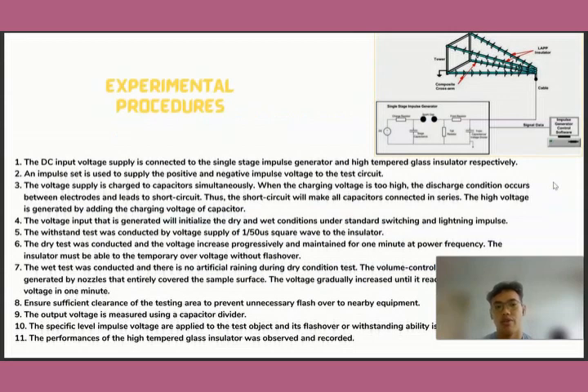For the experimental procedure, there are 11 steps. First, the DC input voltage supply will be connected to the single stage impulse generator and the high tempered glass insulator respectively. Second, we will use the impulse set to supply the positive and negative impulse voltage to test the circuit. Third, the voltage supply charges the capacitor simultaneously, and when the charging voltage is too high, a discharge condition occurs between the electrodes and leads to a short circuit.